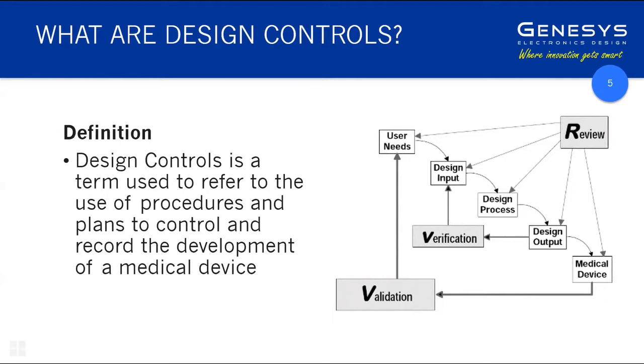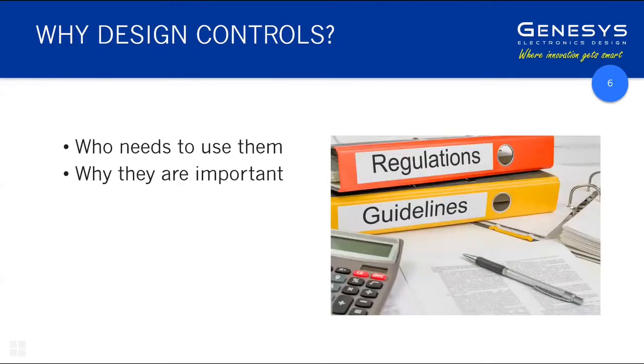Okay, let's move on then. So I started to say, do they all need it? But can you just talk a little bit about why they're needed and why they're important? Well, starting with the second question, they're important because they are prescribed by ISO 13485, which is mandatory to put a medical device legally on the market. So they're not optional, they're actually prescribed in quite some detail in that standard.